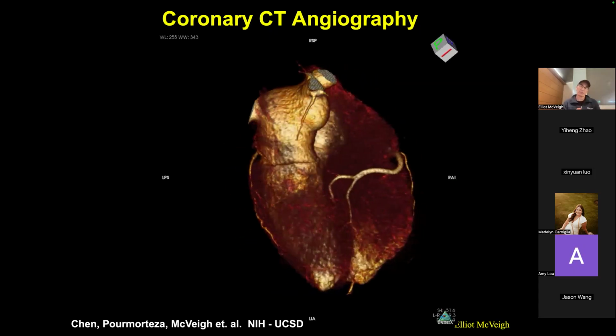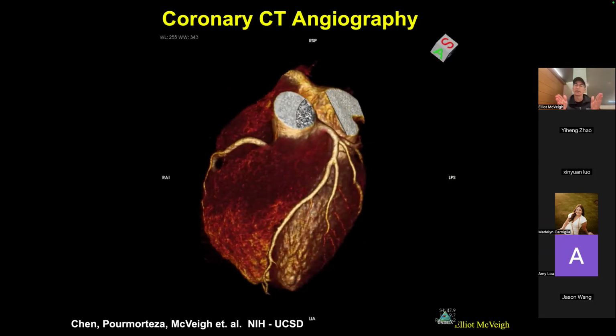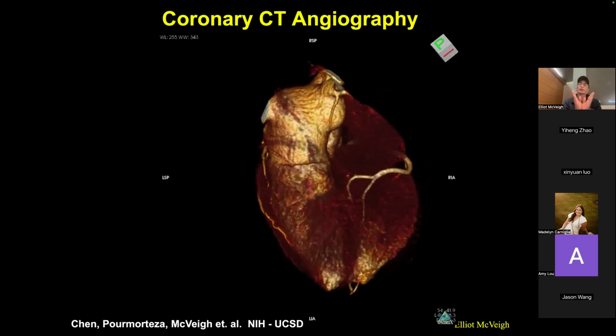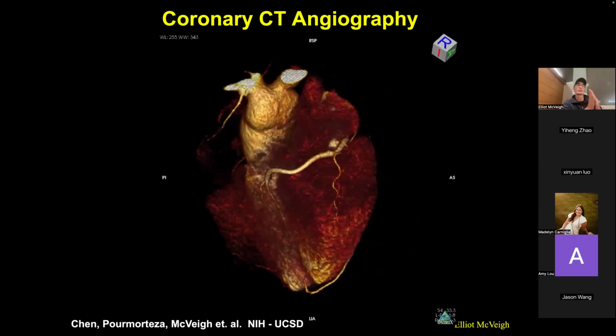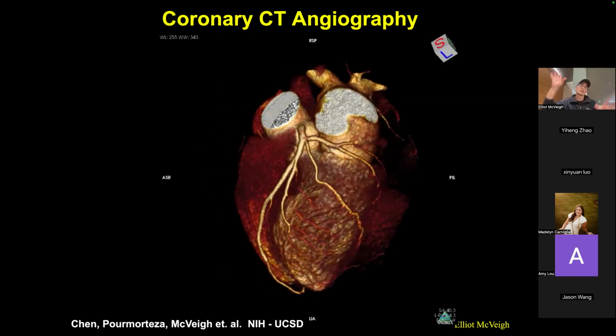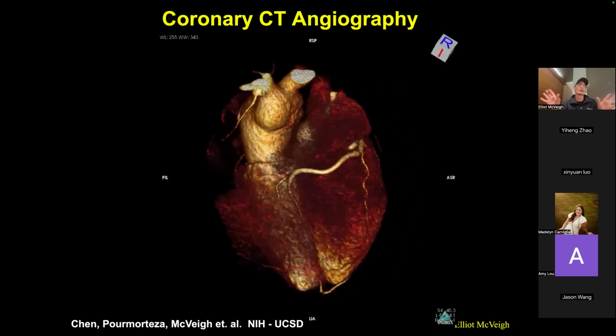We didn't talk about this, but the folks who are doing the difference between parallel beam and fan beam CT will probably show us that when you do fan beam, you can't just do 180 degrees worth of projections. You need to sample a little bit more than that to fill in the edges and get all of the angles.